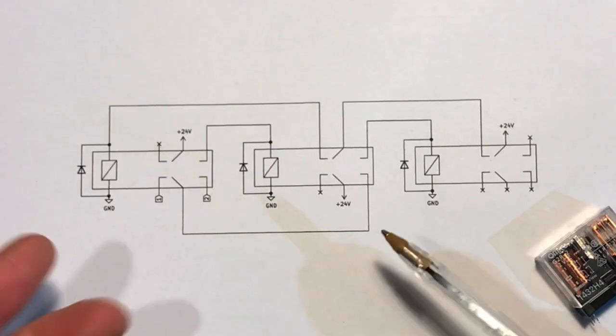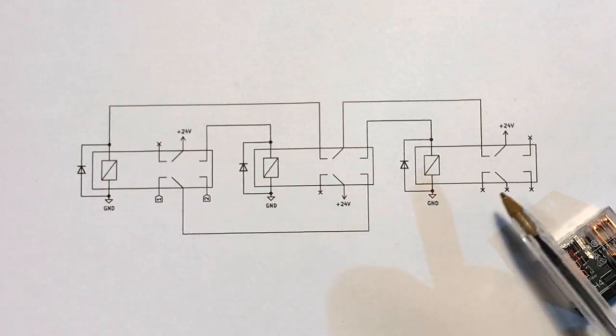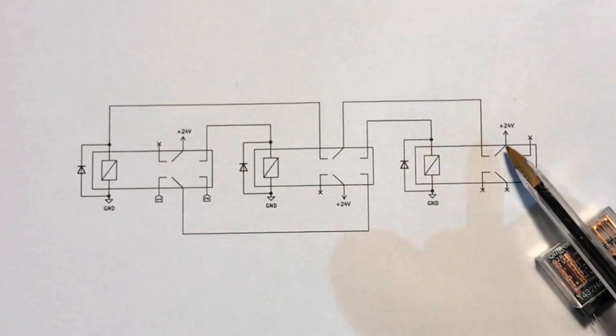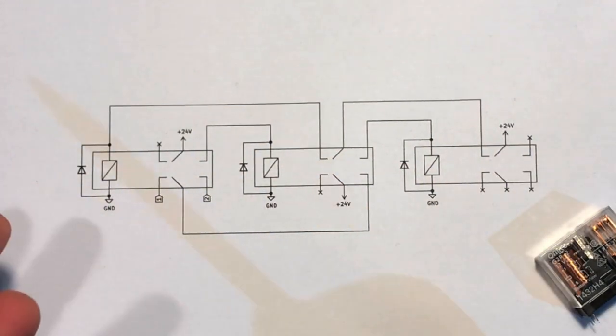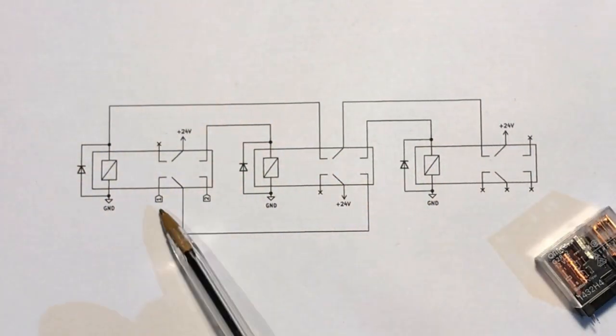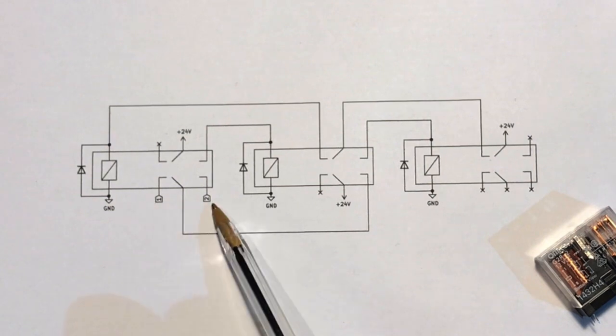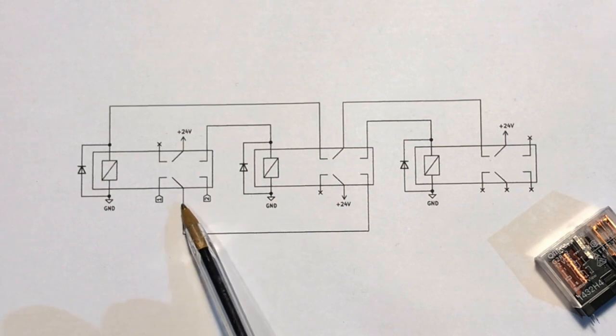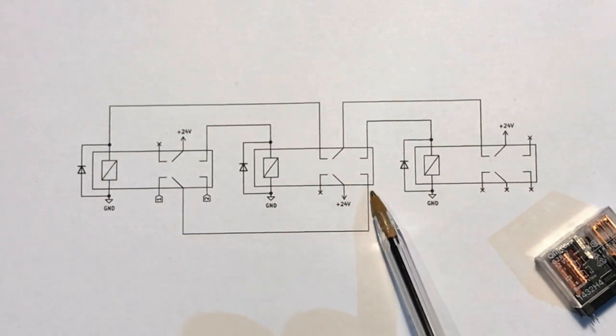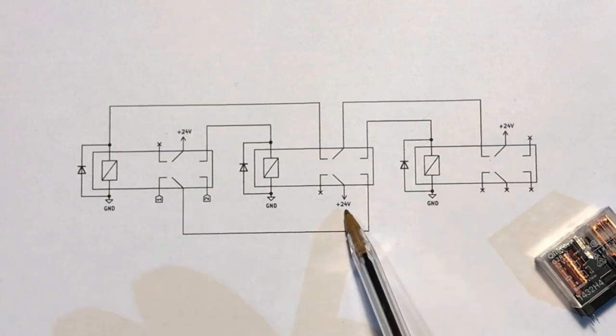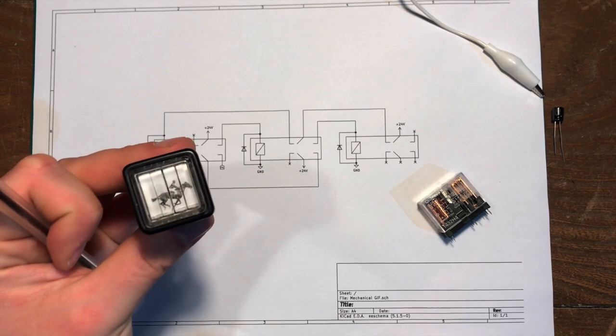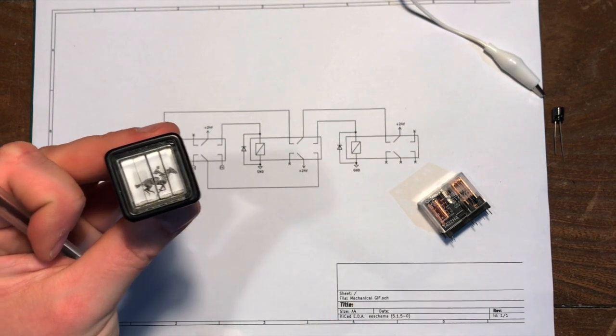So let's just imagine that you've only just turned the power on and all of the relays are in their normally closed position as they're drawn here. Pins one and two of our indicator are connected here, and there's a double throw switch here which can either connect this side or this side to the middle pin. This middle pin, if you follow the wire going all the way around, is connected to this switch terminal. 24 volts connected to the middle pin is not going anywhere. So to begin with our display is just in its middle resting position.